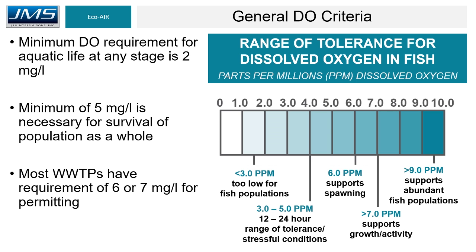General DO criteria: the minimum DO requirement for aquatic life at any stage of life is 2 milligrams per liter. A minimum of 5 milligrams per liter is necessary for survival of the population as a whole, and most wastewater treatment plants have a requirement of 6 or 7 milligrams per liter for permitting. Fish begin leaving areas at 2 to 3 parts per million. Notably, carp only require 1 milligram per liter. Some permits call for DO effluent requirements as high as 7 to 8 milligrams per liter, typically due to the effluent falling into a trout stream.